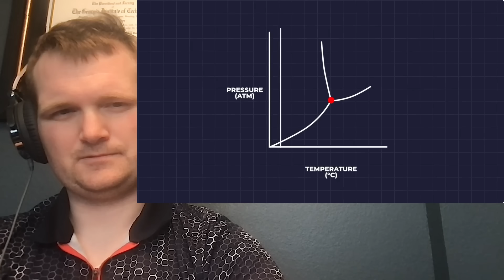This limits the practical thermal efficiency of the steam turbine to about 30 to 35%. But there's another important, less talked about reason for the general limit, which is that if we go any higher, we start to approach the critical point of water, which is about 374 degrees C at 22 megapascals.